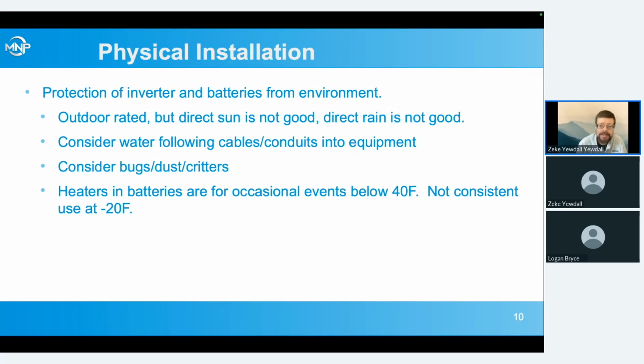Physical installation, continuing, we want to think, what kind of environment are we putting them in? The PowerFlow 16 batteries and the inverter, not the rack mount batteries, but the wall mounts and the inverters, are outdoor rated for NEMA 3R. But direct sun's not good. It destroys the displays on them, and it makes them operate at a much hotter temperature, and that's just not good long term for longevity of electronics. I've seen a lot more failures of even the old string inverters when they were mounted in direct sun than when they weren't, and they were also outdoor rated.